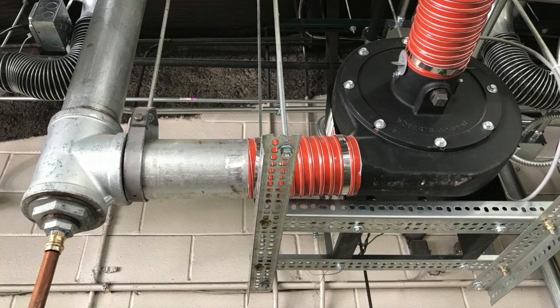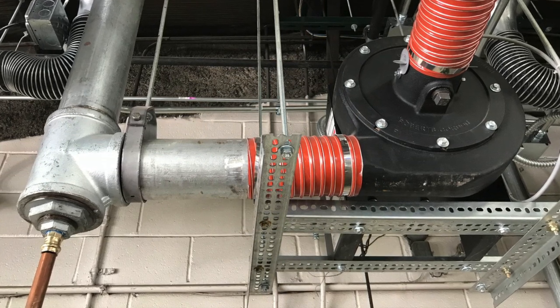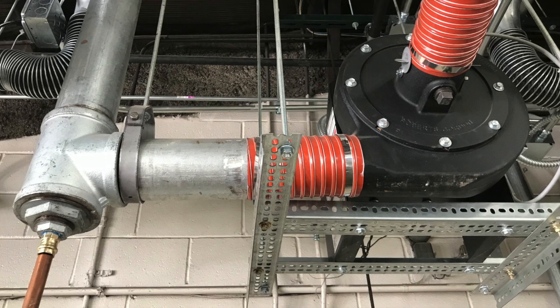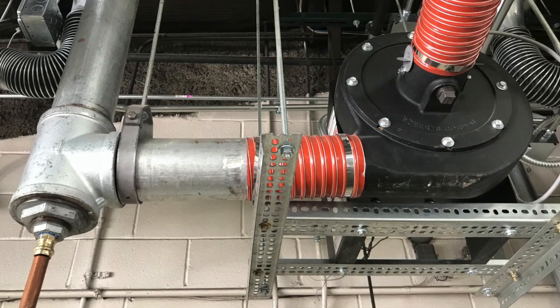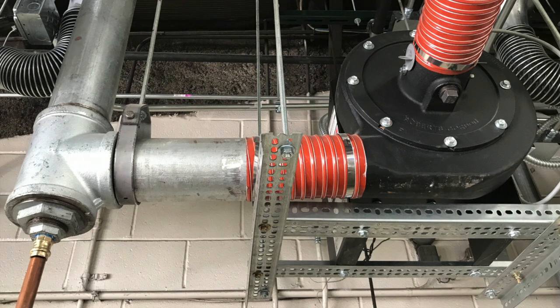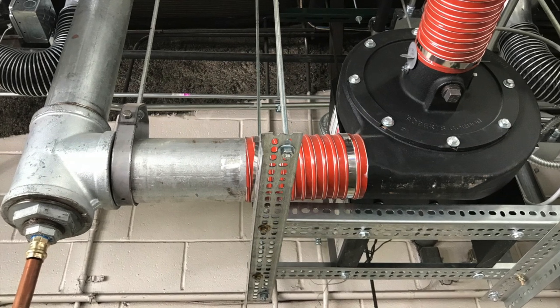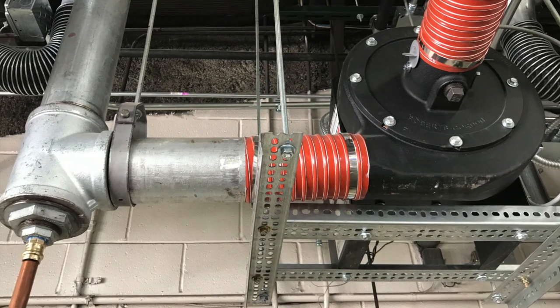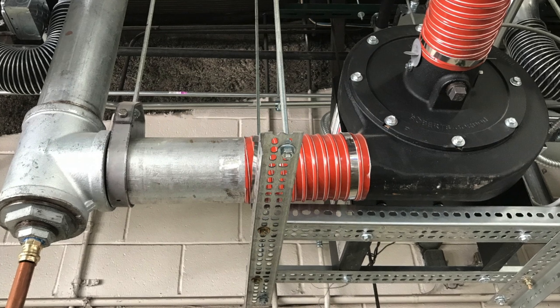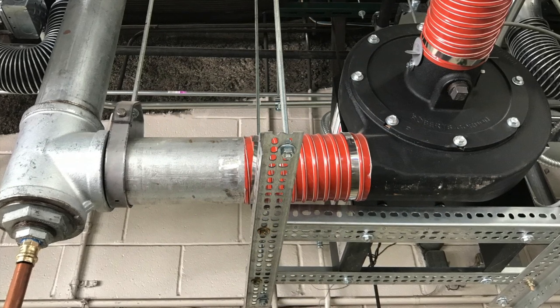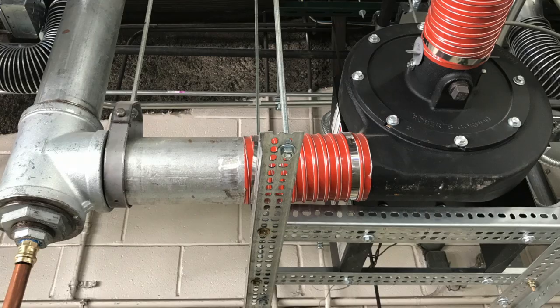Make sure the 1/8 inch barb fitting is on top of the inlet. You have to remove the 1/8 inch plug and install the brass barb fitting. The 1 inch hole in the bottom of the inlet must be plugged with a 1 inch MPT galvy plug. When installing the vacuum pump to the system, make sure the vacuum pump is aligned with the pipe.